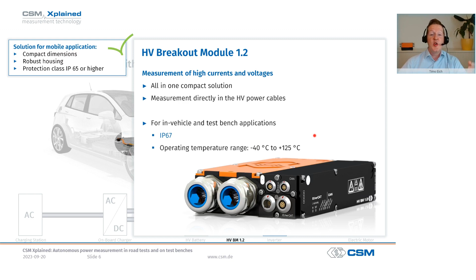Because our HVBM 1.2 now measures the HV voltage and current directly and without any analog transmission path exactly where they occur. Therefore, the HVBM has to be robust, and as you can see, the HVBM offers IP67 protection and an operating temperature range of -40 up to 125 degrees centigrade. So you could get started in winter testing as well as in the desert.